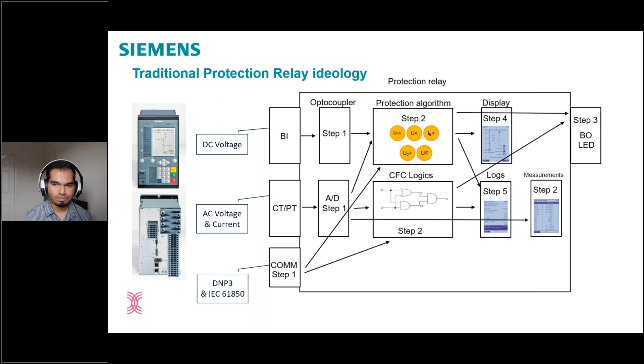So how do we achieve this digital twin capability? Just 4 steps. The digital twin application is stored in the cloud and it can be accessed anytime, anywhere using a web browser. We call it the 4-step approach. Step 1: you create a configuration using the DIGSI 5 software, which is a configuration software for Siemens protection relays. Through the software, you export a configuration file in a .sim format, which has all the data for that particular relay or multiple relays. You then import the SIM file in the Siprotec Digital Twin application, which is done via a web browser. And then you power up the relay and test to validate your results and validate how the relay is performing. So that's how simple it is.